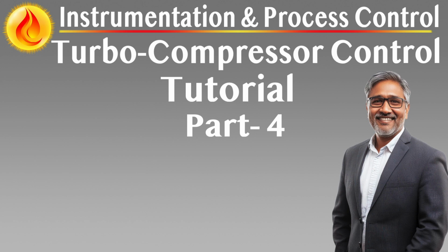Anti-surge valve instrumentation. The surge control valves must be equipped with high-speed positioners, position feedback transmitters, and integrated diagnostics. These valves must meet tight control and fast response requirements as they serve both surge protection and process recycle functions. Skid edge interface and layout. All signal wiring from field devices is routed to explosion-proof or weatherproof junction boxes at the skid edge. These boxes are clearly labeled and include terminal strips for quick connection to site cabling.